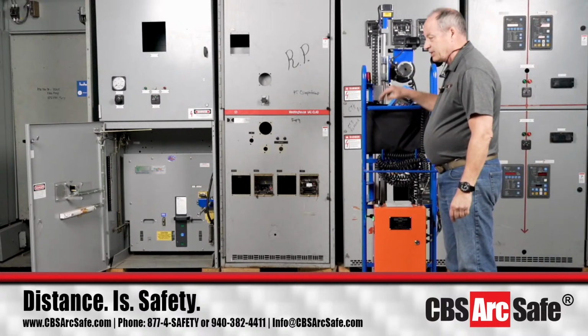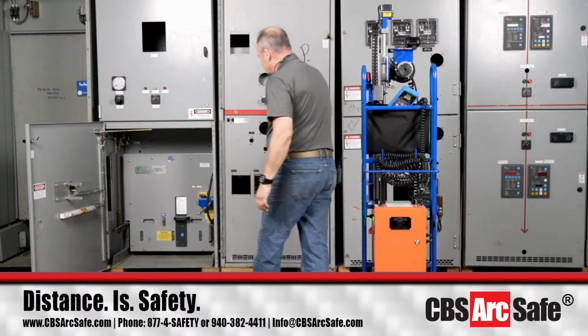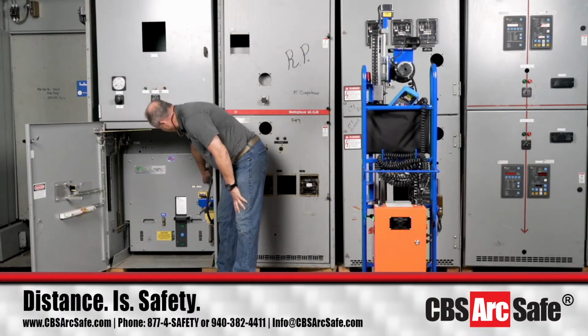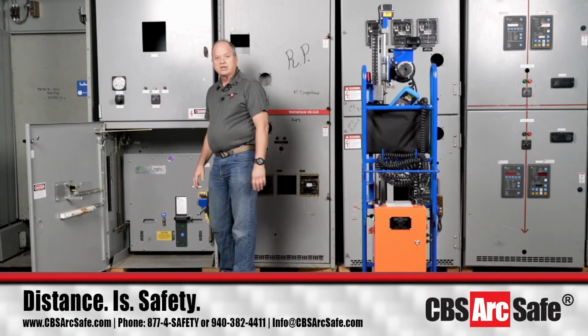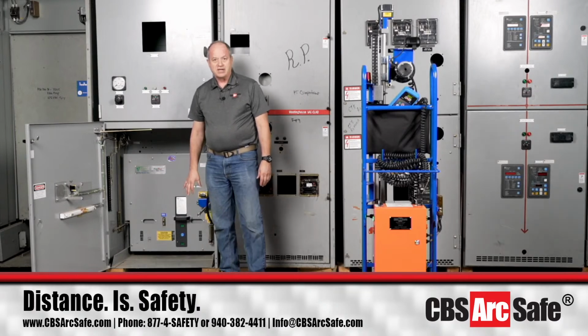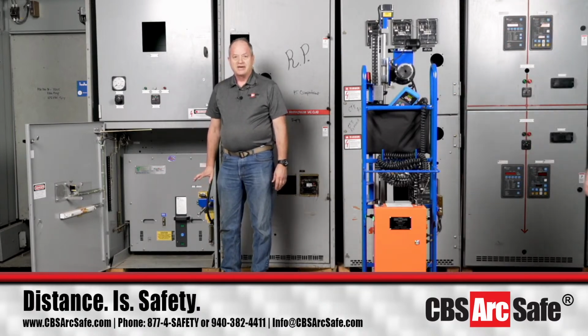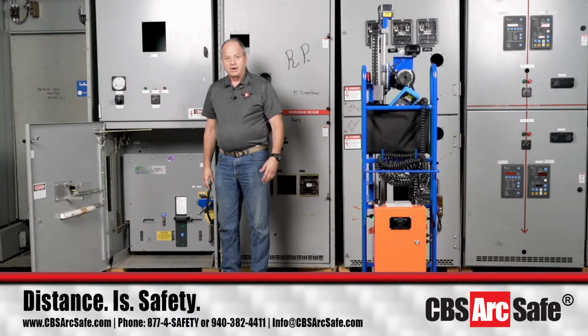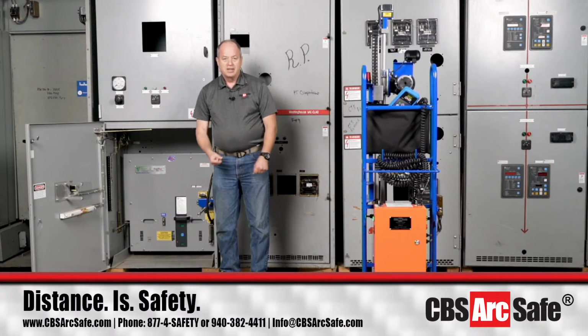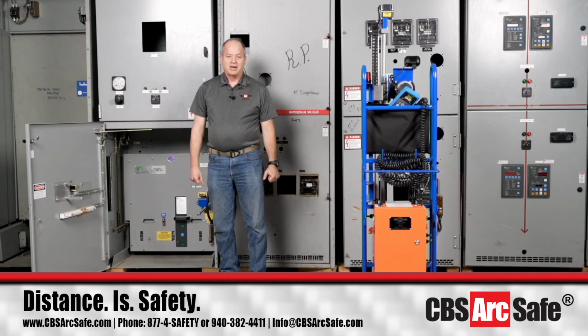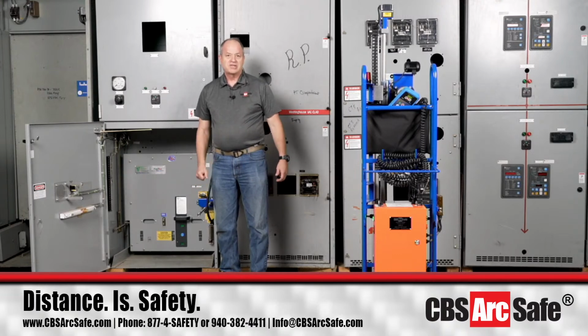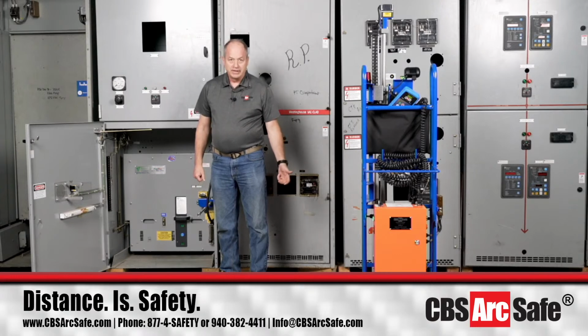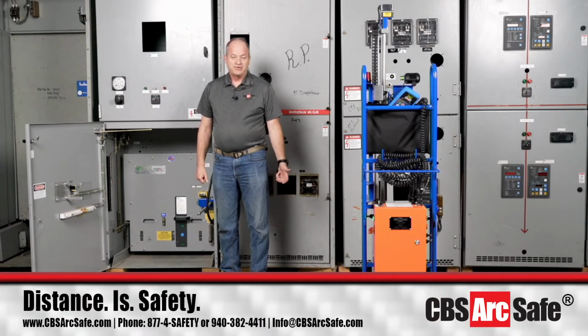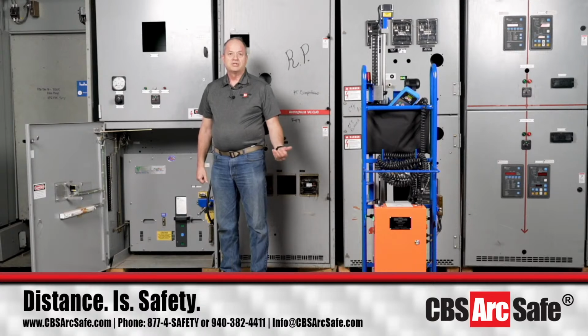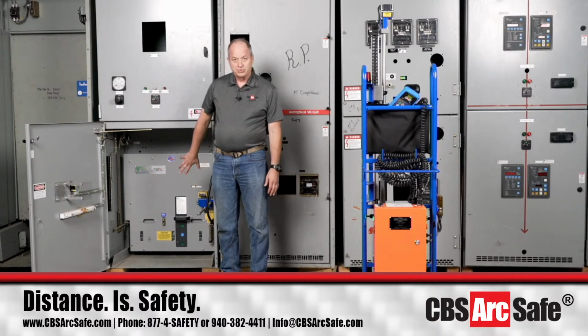One of the things I'll point out before I put the machine up here is this: normally you've got a label here which says disconnect, test, and connect. Sometimes when you get a little wear and tear in these racking mechanisms, you may have racked it in physically all the way, but you're past the actual interlock for the operation. You may have to back it off and center the word connect in the window to get the breaker to properly function. That's one of the things you need to note and understand about this family of switchgear.